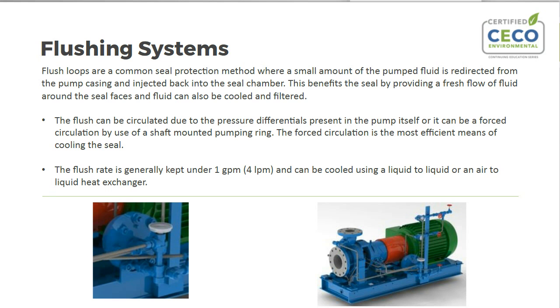With that in mind, it's always pushing that fluid through, and the differential pressure between the discharge of the pump and the seal chamber is always going to be enough that you're going to continue to get a significant amount of flow. Typical flush flow rates are anywhere from a quarter GPM to maybe 1 GPM. So the flush fluid rates are generally very, very low. Another method is called Plan 23.